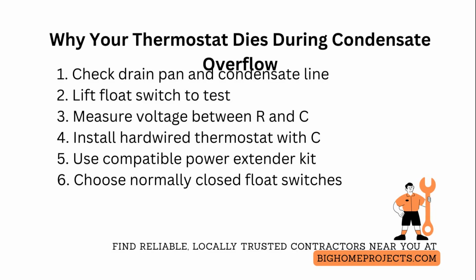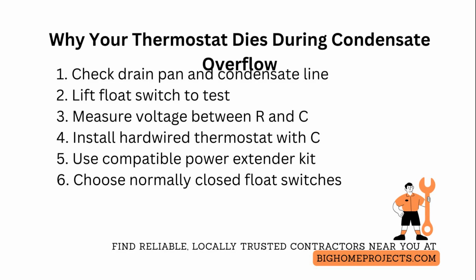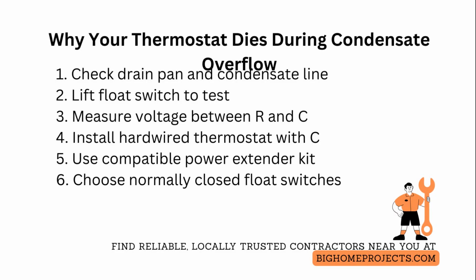Second, measure voltage between the R and C terminals with a multimeter. You want about 24 volts AC when the float is not tripped. If you only see battery voltage or nothing, you likely lack a proper common wire.